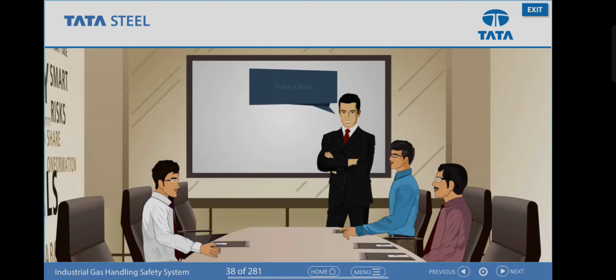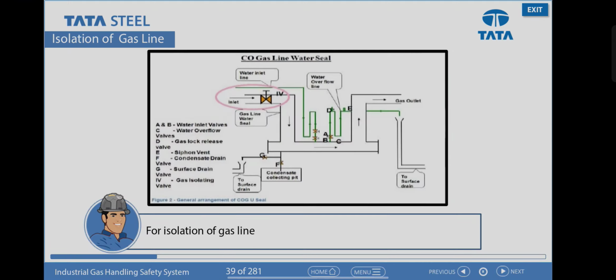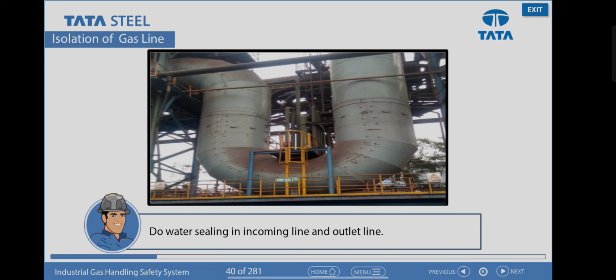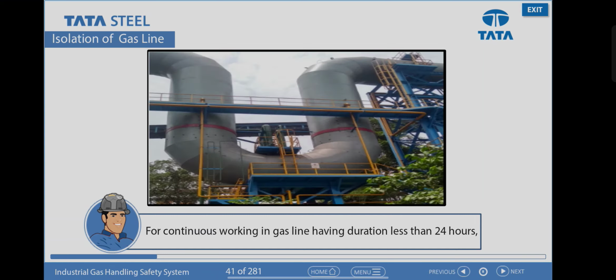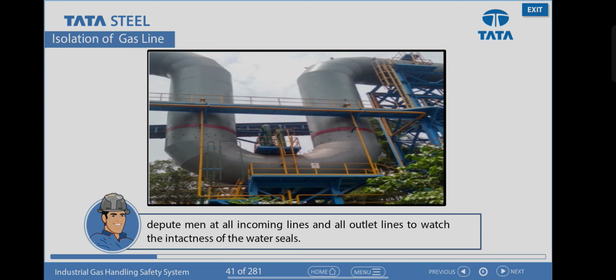Take a look. For isolation of gas line, close the gas incoming and outlet line valve. Do water sealing in incoming line and outlet line. For continuous working in gas line having duration less than 24 hours, depute men at all incoming lines and all outlet lines to watch the intactness of the water seals.